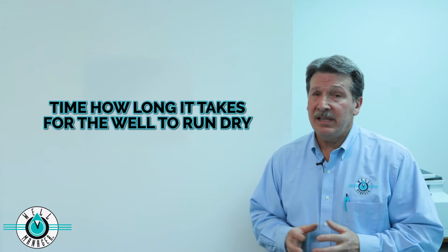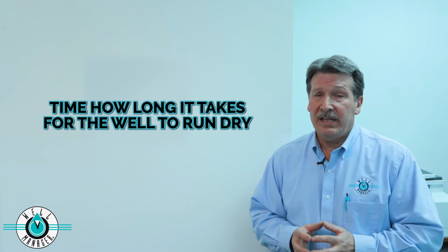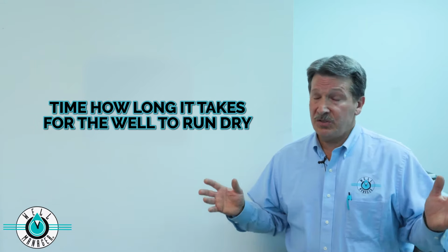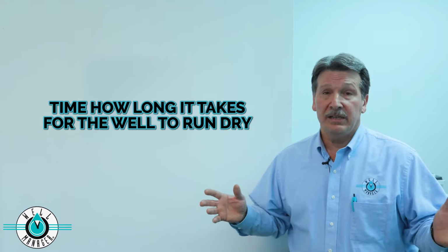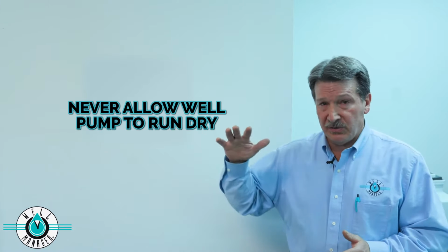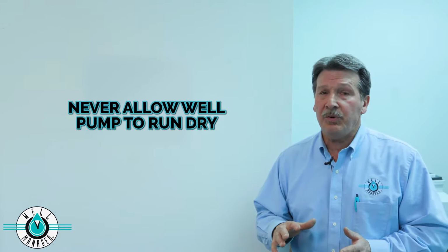So then you would get your stopwatch out and you would turn that spigot on and let it run until the well goes dry. Need to remember, you have to shut the power off at that point because we never want the well pump to run dry. But you'll see a severe drop in the pressure output, indicating that the well is dry. Shut it off. Estimate, did that pump just run for 10 minutes or 20 minutes?